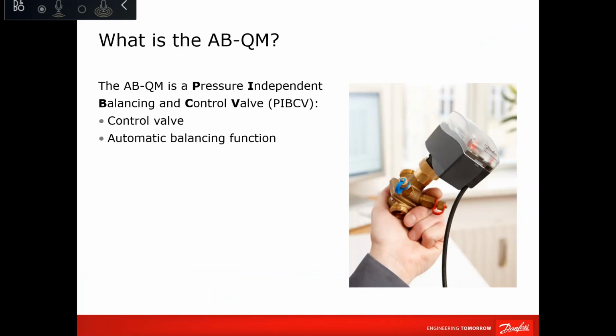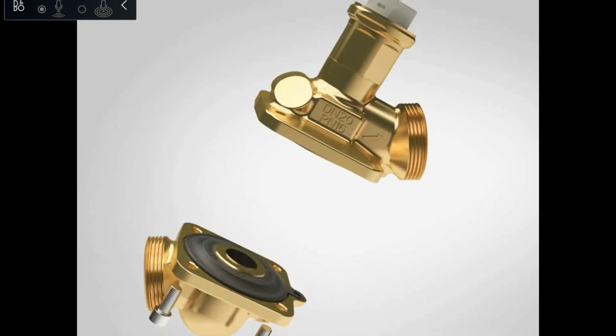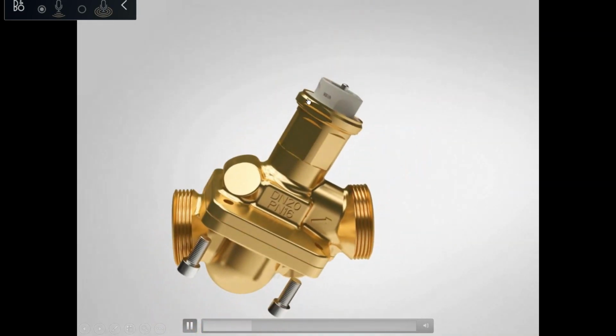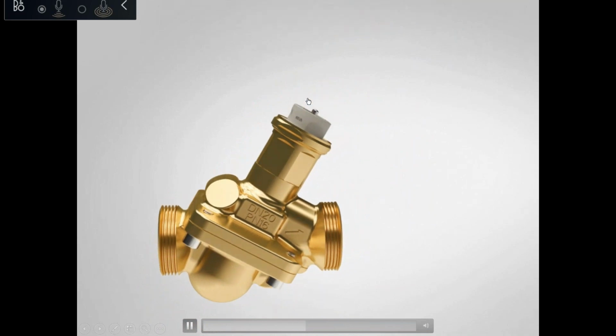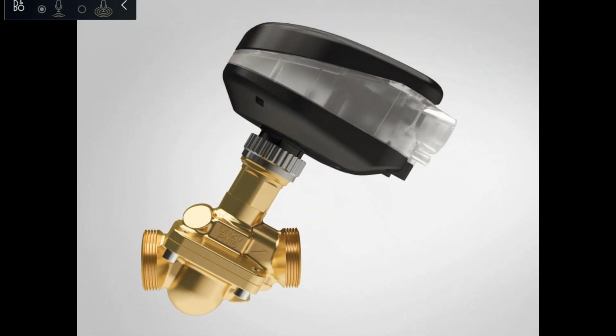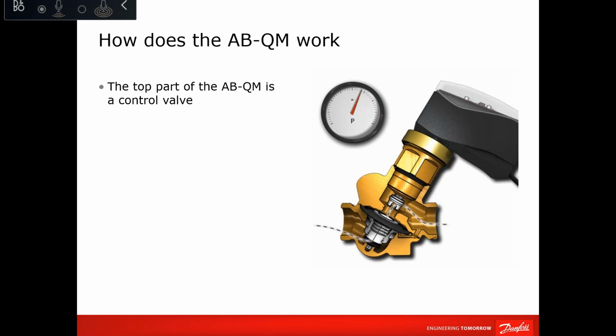Now if we move to our valve, the PIBCV, the pressure independent balancing and control valve, is a control valve with automatic balancing function, which means DPCV plus the control valve. So here you can see clearly: the lower part is the differential pressure controller, the upper part is the control valve, and they're just fixed together, and this we will talk about later. So here, if we see how the valve is working, it's very simple. The flow direction is shown here.